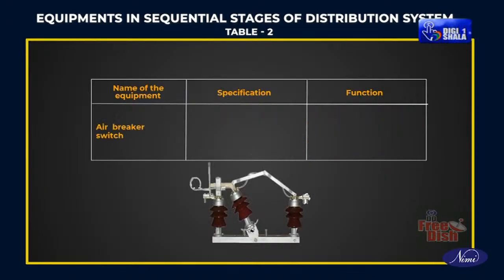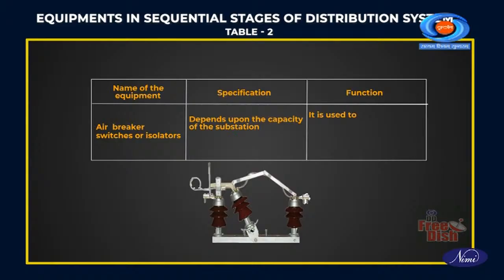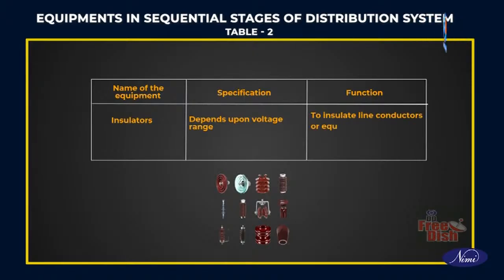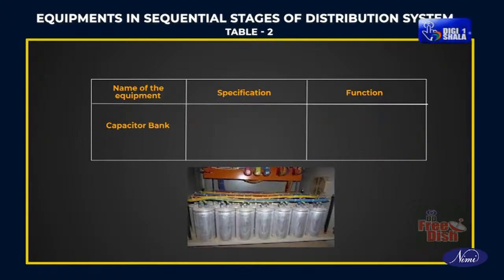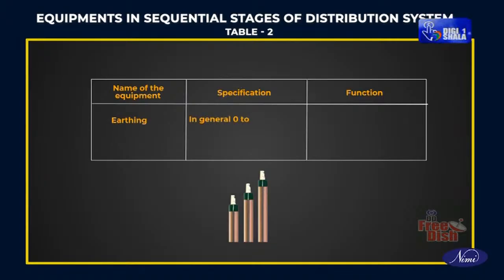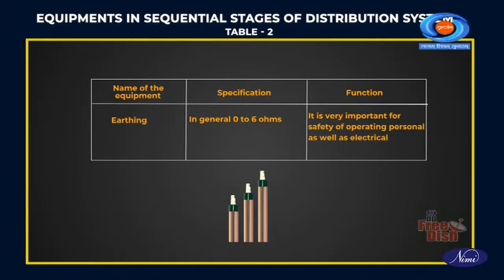Air break switches or isolators depends upon the capacity of the substation. It is used to isolate equipment for maintenance or replacement, and that can be operated manually. Insulators depends upon voltage range. To insulate line conductors or equipment at different voltages with respect to the ground structure. Capacitor bank depending upon capacity of substation. To improve power factor. Earthing in general 0 to 6 ohms. It is very important for safety of operating personnel as well as electrical devices.